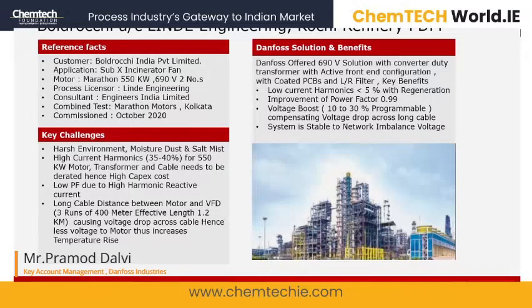And the third very important point is when the input voltage is fluctuating or in imbalance. In that case, the active front-end drives will ensure a steady state DC voltage, so your system is also stable. So these are the key benefits that the active front-end solution and LR filter will give.